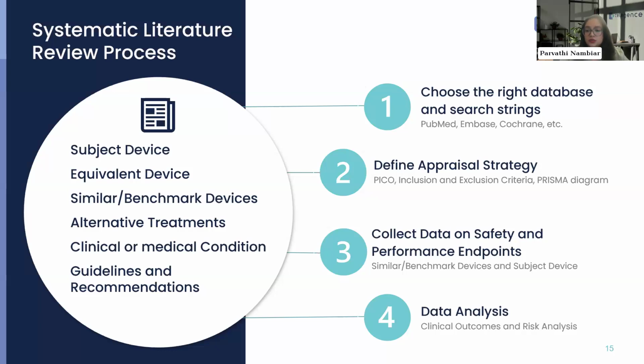The inclusion and exclusion criteria are established based on the type of the device and the risk classification to obtain the most relevant and correct data. PRISMA protocol is to be followed, and I will talk about this in the next slide. The aim of the review should be to obtain relevant data on the safety and performance endpoints. This can be obtained from literature published on the similar or benchmark devices, and these will be used to establish the acceptance criteria for this evaluation.